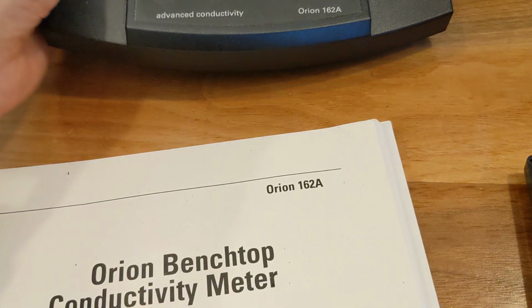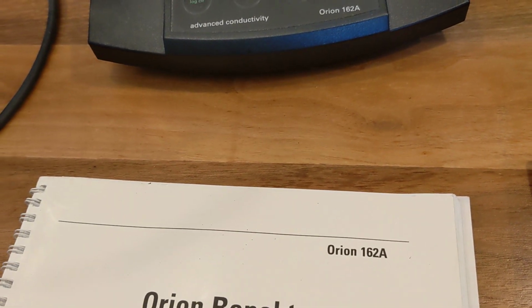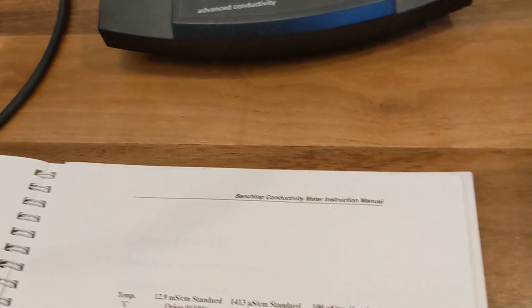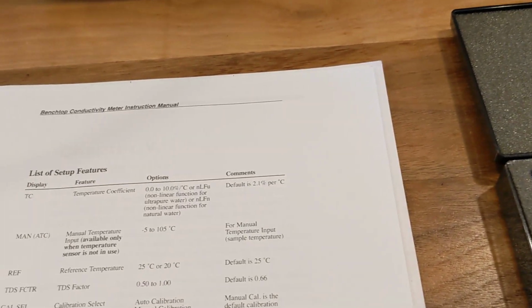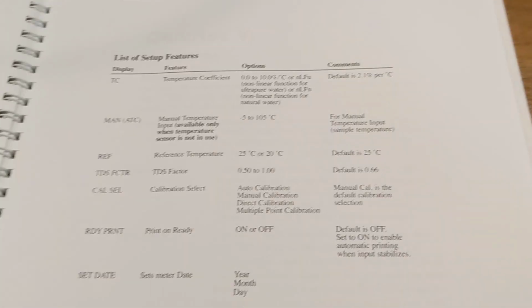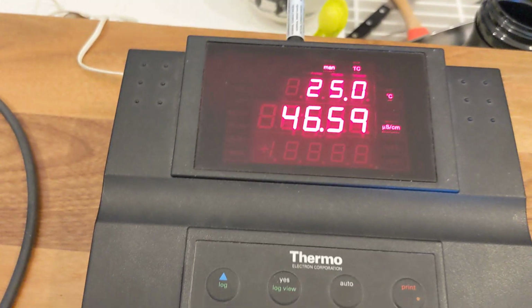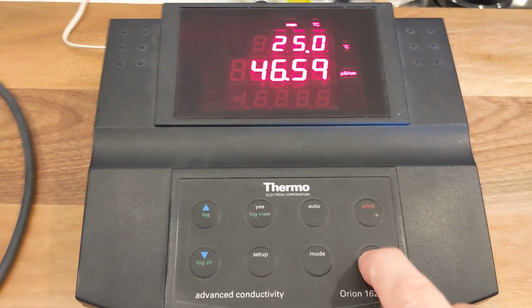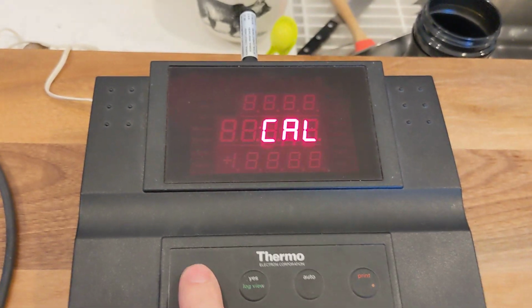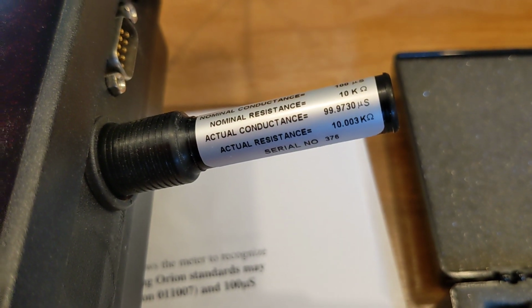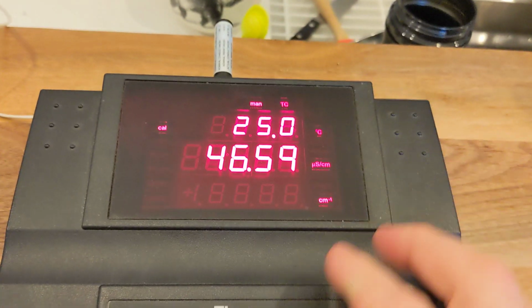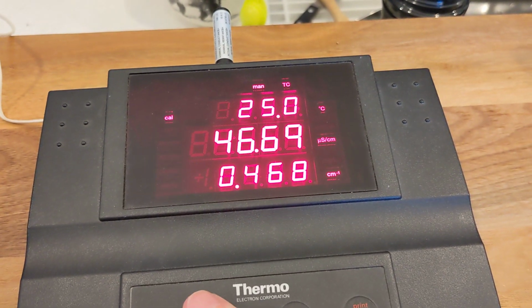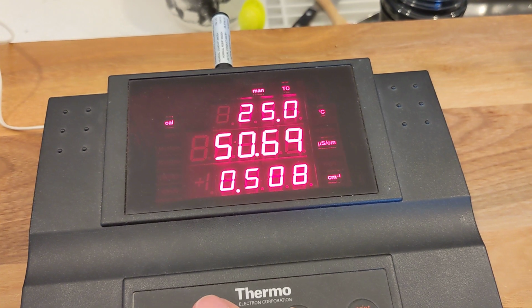So can we calibrate this? Maybe that battery is dead. All right, let's take a look at that. Well, it turns out we can calibrate it with this here cal button. So cal manual, and we need this to read 99.9730. So let's do it. It's a long way off.